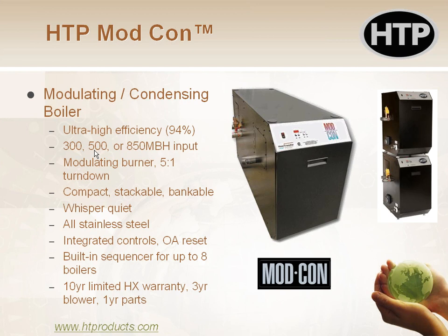All right, if you need bigger than 399,000 BTUs, there's yet an even bigger brother to that other boiler. It's called the ModCon, and ModCon stands for modulating condensing. It's 94% efficient for all 3 sizes. The sizes available are 300, 500, and 850,000 MBH input. It's a 5-to-1 turn down, so we can modulate from 100% down to 20% on a single boiler. And if I have 2 boilers, I'd be able to modulate from 100% down to 10%. If I had 4 boilers, I can go from 100% down to 5%. I can keep scaling that back. Some of the really cool things about these boilers: they have the same controls I just talked to you about a minute ago. So they have outside air reset built in.